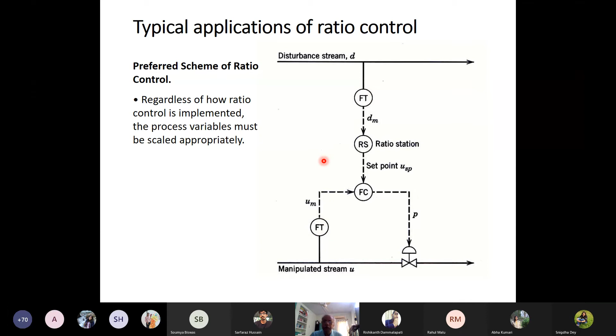However, regardless of how ratio control is implemented, whether it's method 1 or method 2, the process variable must be scaled appropriately. This basically means you have a flow transmitter over here and a flow transmitter over here. The flow transmitter scaling has to be done properly so that they are on the same level. Unless you do that, the gain setting will not be appropriate. So normally we put KR equal to R_D times S_D by S_U.